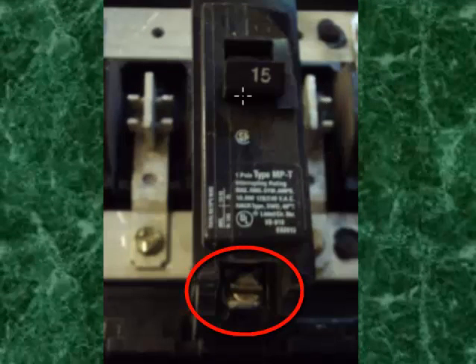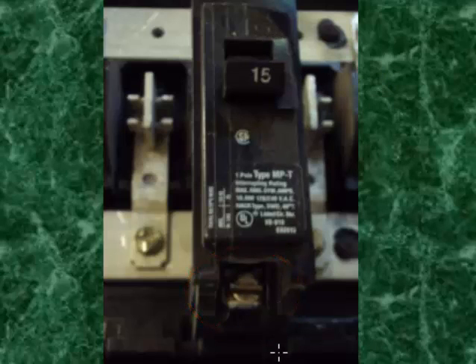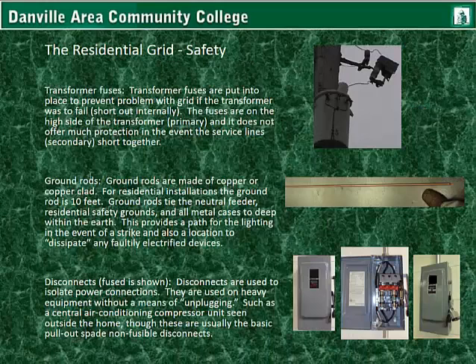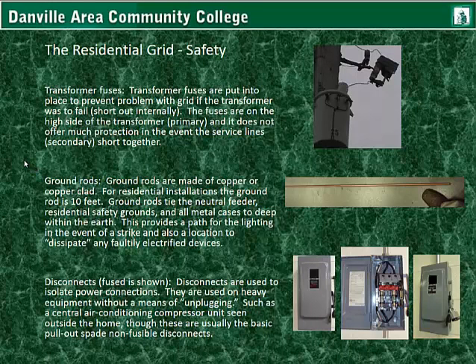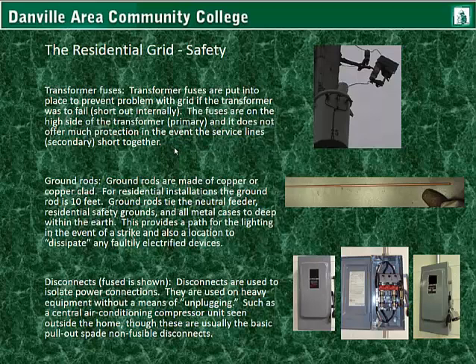Here's a breaker — it just locks into position on the lugs, and there's a screw terminal that comes out of it. The breakers are for overcurrent protection, but they can also be used to feed power into a panel. In addition to the safety of having a breaker box, I want to backtrack and talk about the transformer fuses. Transformer fuses are put into place to prevent problems with the grid if the transformer was to fail. The fuses are on the high side of the transformer's primary, and it does not offer much protection in the event the service lines short together. Sometimes it'll pop, but the transformer can get overheated and eventually explode.